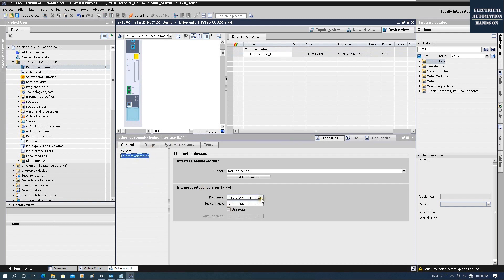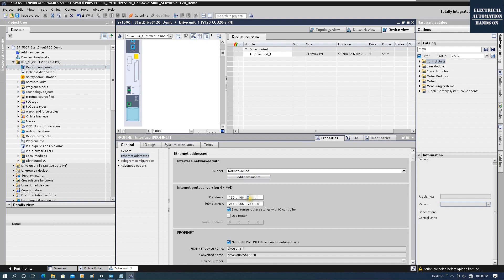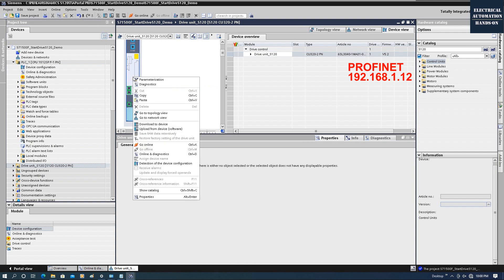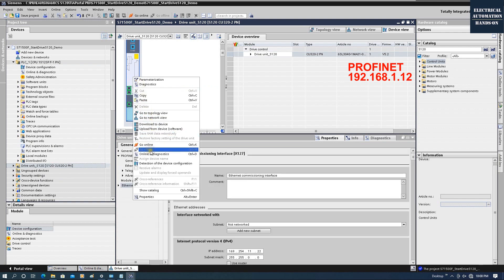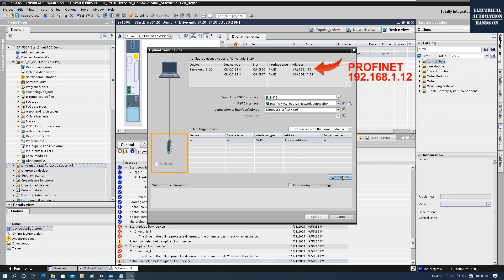The commissioning port uses IP address 169.254.x.x. Make sure we are not selecting this — we need to select the PROFINET port. For my PROFINET port, I will configure IP address 192.168.1.12. Then we can right-click on this CU and click 'Upload from device' to upload all the configuration from the actual hardware.